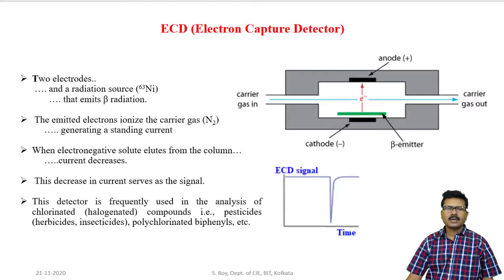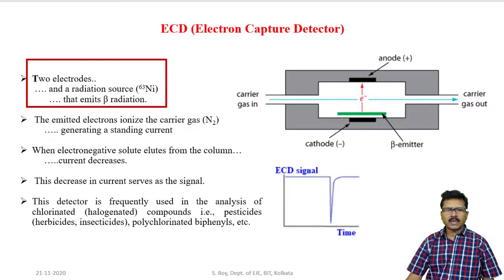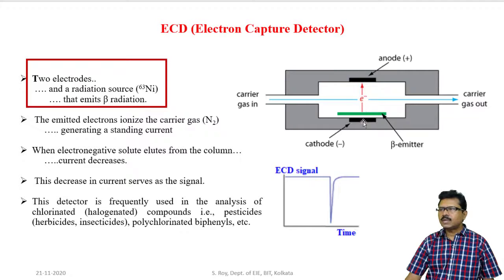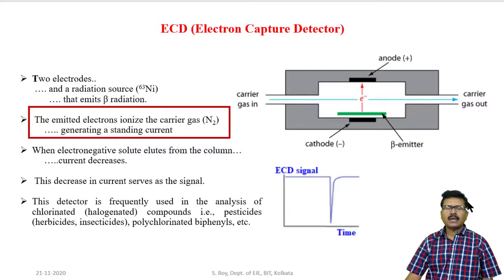Next, coming to electron capture detector. By the name, we can understand there will be an electron-capturing phenomenon. In the electron capture detector, two electrodes are present in the cavity — one is anode and the other is cathode — along with a radiation source. Normally nickel-63 is used as the radiation source, which emits electrons. In normal process there will be a flow of electrons from cathode side to anode side. Normally nitrogen gas is used as carrier. When simple carrier gas passes through this cavity, emitted electrons ionize the carrier gas and there will be a constant flow of electrons from cathode to anode, producing a constant current through the external circuit.